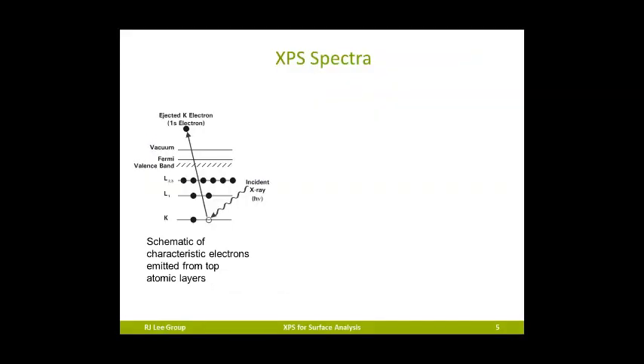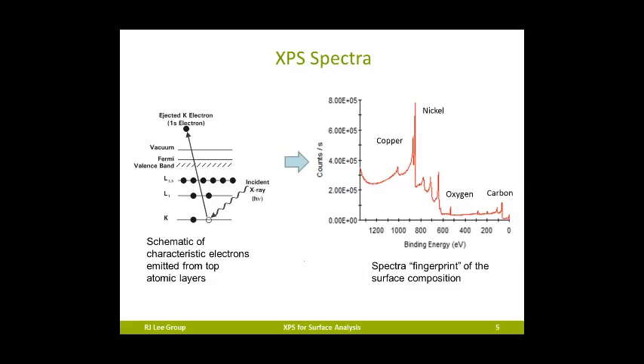XPS achieves surface sensitivity by shining a monochromatic X-ray beam onto the surface of a sample in a high vacuum chamber. The X-ray beam causes signature electrons in the elements on the top surface to be emitted and collected. These signature electrons have a specific energy spectra or fingerprint depending on the element and its chemical bonding state. This fingerprint of surface atom configuration is then interpreted by computer analyses and the experience of XPS surface scientists to determine the elements and chemical states on the surface of a material.